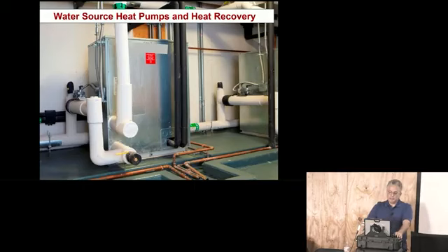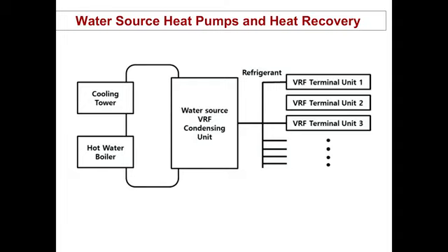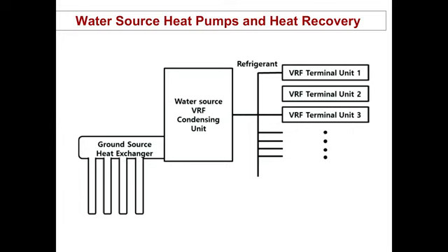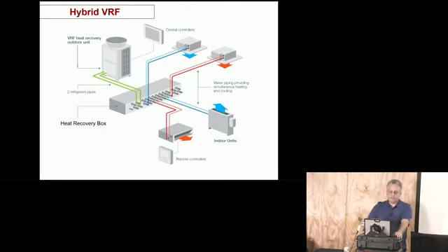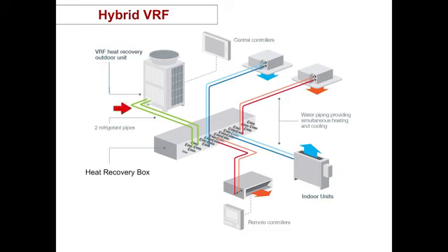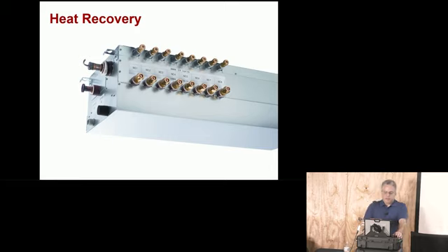Then we have water source heat pumps and heat recovery. Most major manufacturers have this product available. So you can imagine that you have a water system, and instead of running it through your chiller and boiler, you just run it through the VRF. And if you have a ground source heat exchanger, otherwise known as geothermal, you can do that as well. Then you have what is touted as hybrid VRF, which is basically using both water and refrigerant. The green here in the illustration is refrigerant, and then you have that heat recovery box can produce either cool, chilled water or hot water. So the heat recovery box.